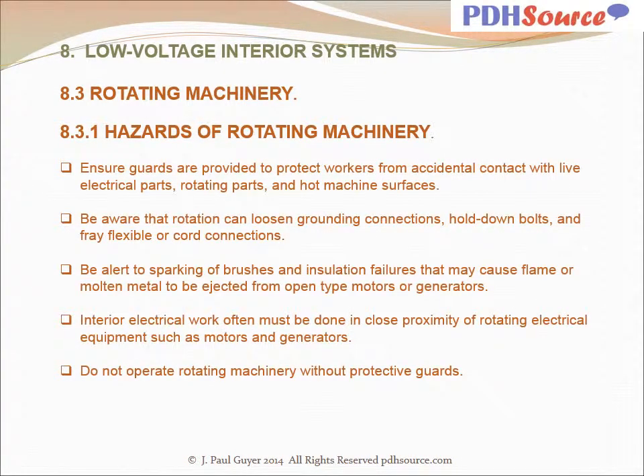Now, some comments on hazards associated with rotating machinery. Ensure that guards are provided to protect workers from accidental contact with live electrical parts, rotating parts, and hot machine surfaces. Be aware that rotation can loosen grounding connections, hold down bolts, and fray flexible or cord connections. Be alert to sparking of brushes and insulation failures that may cause flame or molten metal to be ejected from open-type motors or generators. Interior electrical work often must be done in close proximity of rotating electrical equipment such as motors and generators. Do not operate rotating machinery without protective guards.